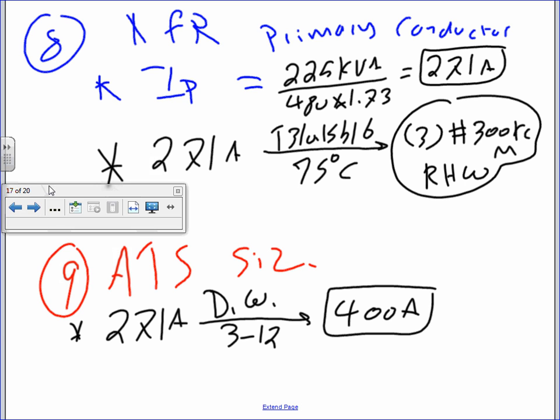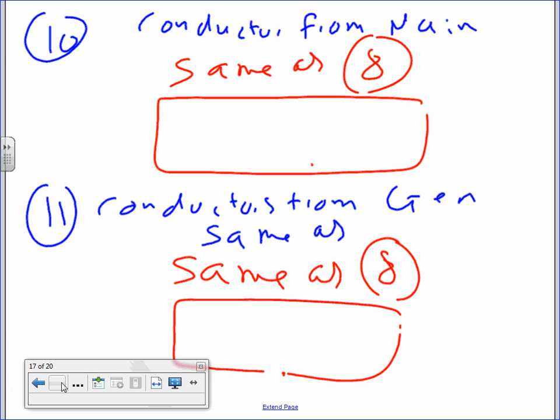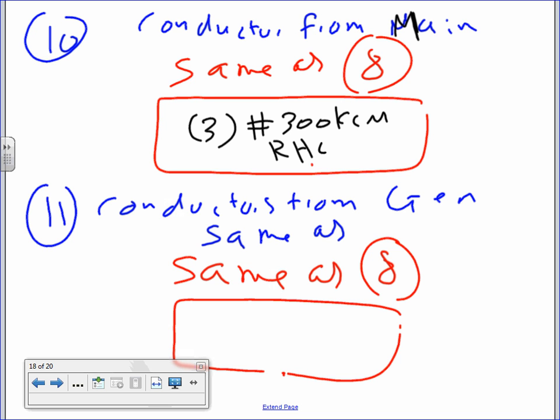All right, so any questions, guys, about these? We got these. Let's go to conductor from the main. This is a main, believe it or not, here. Conductor from the main, same as 8. So do we need to even do any calculation? It'll be 3 conductors, 300 kcmil RHW. How about conductors from the generator? Same as the main, same as number 8. We already calculated: 3 conductors, 300 kcmil RHW.